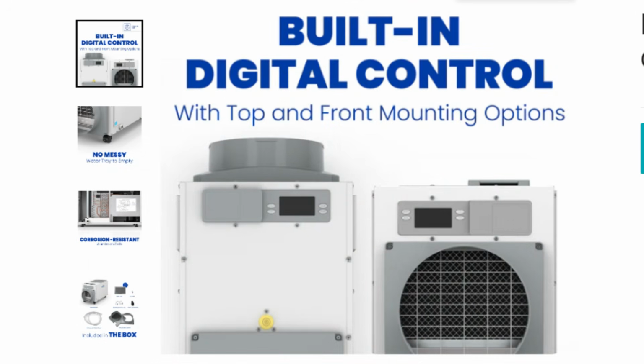The dehumidifier comes with a controller that's mounted directly to it that we use to set the humidity levels. So once every 60 minutes, the dehumidifier is going to come on and sample the air to see how humid it is. If the air is too humid, it is then going to start dehumidifying. And since the dehumidifier is coupled with the blower on your furnace, that means the air is cycling throughout your entire house, resulting in whole home dehumidification. These units also come with washable filters and should be cleaned once every 6 months.